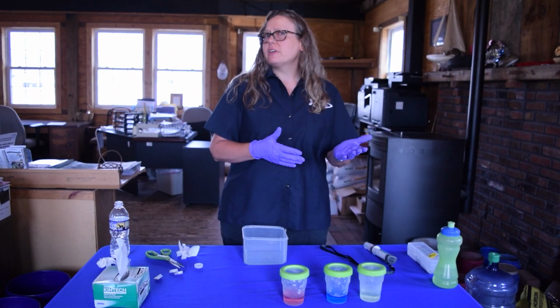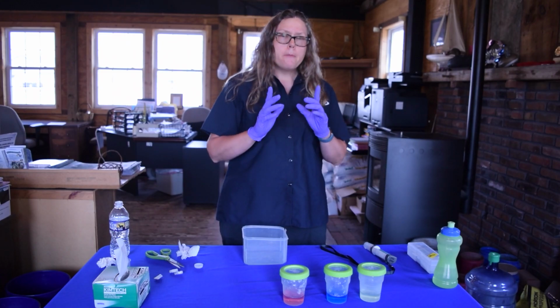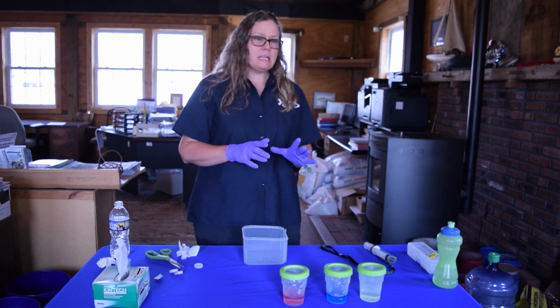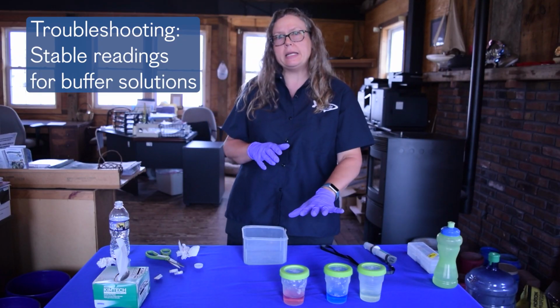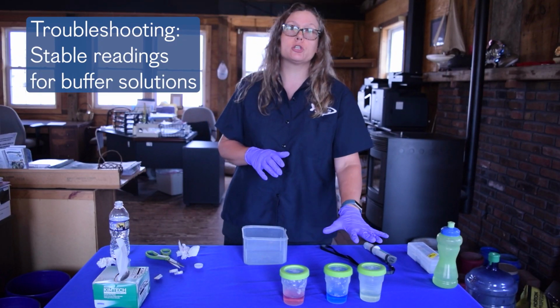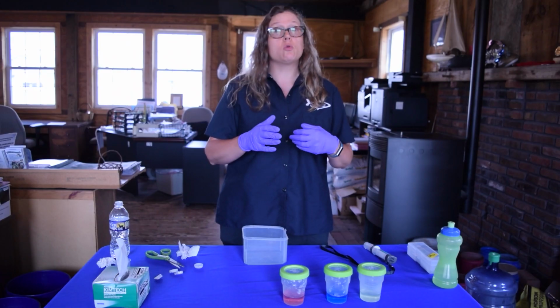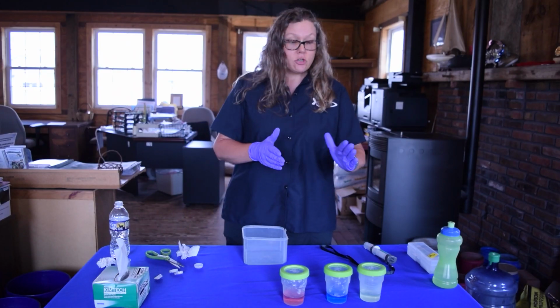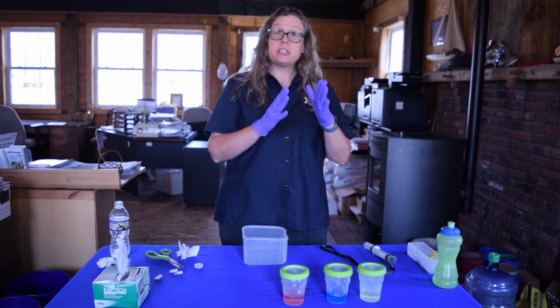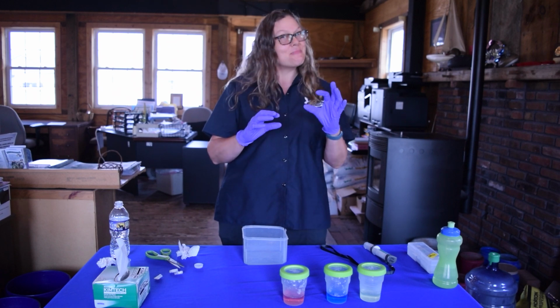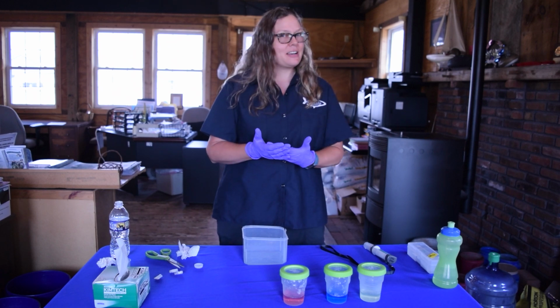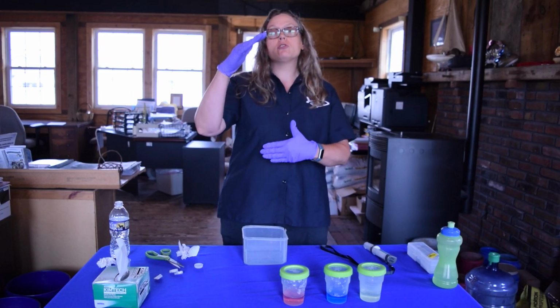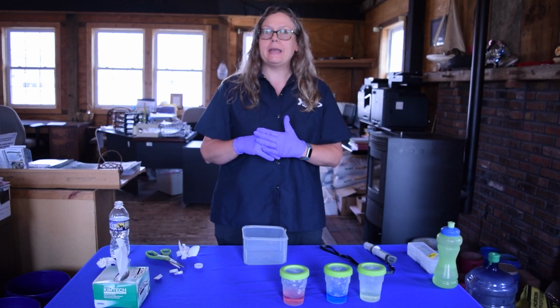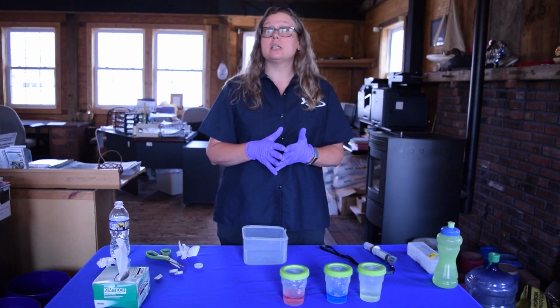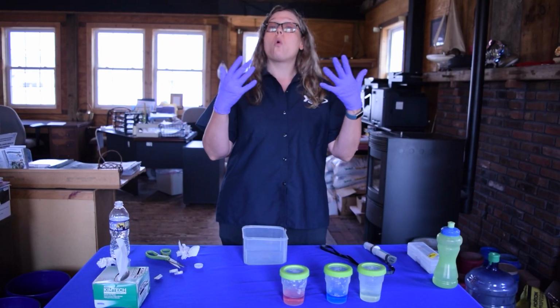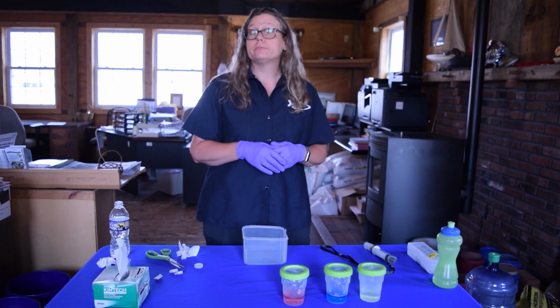There aren't a lot of things that can go wrong when you're calibrating, but one thing that you need to keep in mind is that you need to have stable readings for all three buffer solutions, or else the instrument is not going to be calibrated correctly. Each of these buffer solutions should have stable readings, which means that you'll see the smiley face for about 5 seconds. If you're not seeing that and the numbers are wildly fluctuating, going up and down, you should contact staff immediately so that we can help you troubleshoot or get you a new pH meter.